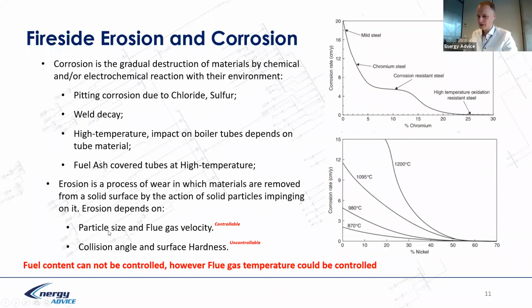So that's for the corrosion effect. And for the erosion effect, erosion depends on particle size and flue gas velocity. And these parameters are controllable, in fact, through the burning process. If you control the burning process, we can control these parameters. However, other causes of erosion are the collision angle or surface hardness. These are probably uncontrollable during the burning process, so we cannot impact them. But fuel content cannot be controlled.